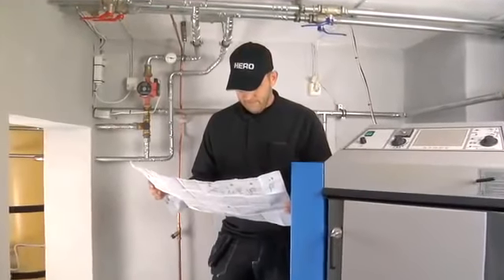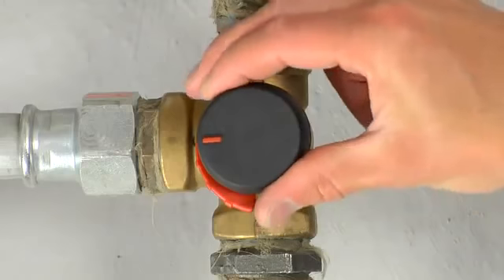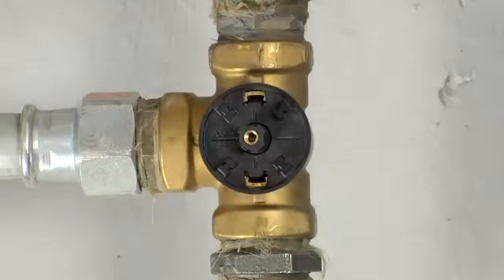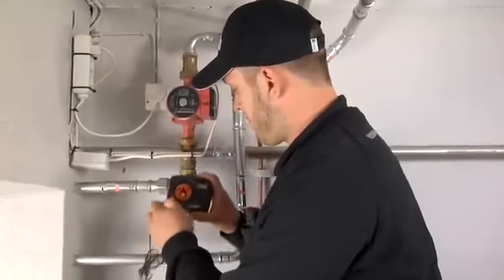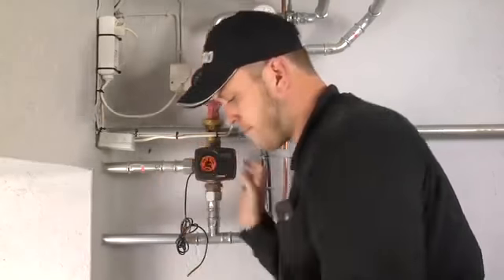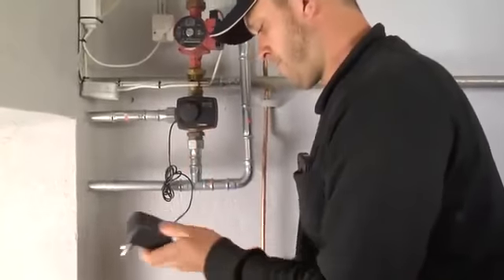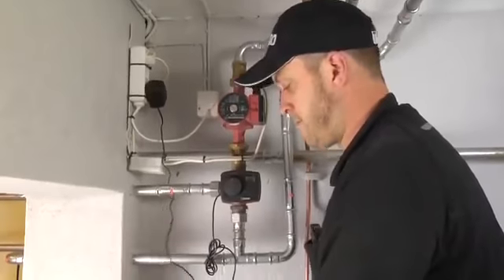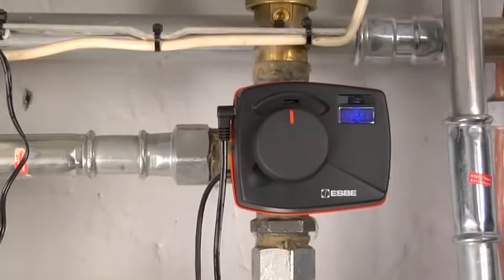ESBE recommends that you always read the instructions for use prior to installation. They provide several good examples of applications similar to your project. Here you can see that the valve opening is to the left. The first step is to remove the knob and graduated disc from the valve. Next you fit the shaft coupling, then the actuator unit and the screw. Set the direction of flow by moving the joystick to the right for right opening or left for left opening and holding it there. Then connect power to the actuator unit. Wait a few seconds before releasing the joystick. Direction of flow is now correctly set.